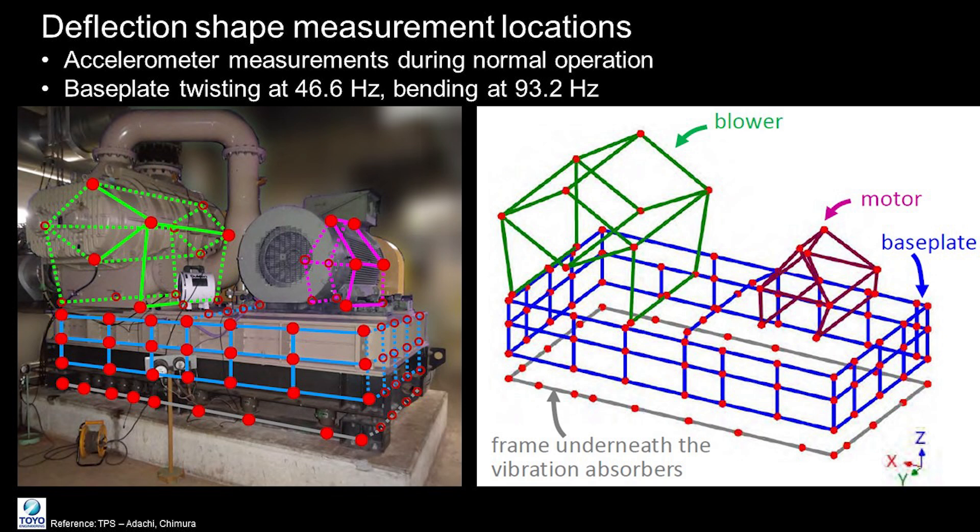To gain a deeper understanding of vibrational behavior, operating deflection shape measurements were conducted using accelerometers. The red dots in the diagram indicate the measurement locations, and the measurements found that the base plate exhibits twisting and bending motions at the excitation frequencies during normal operation.